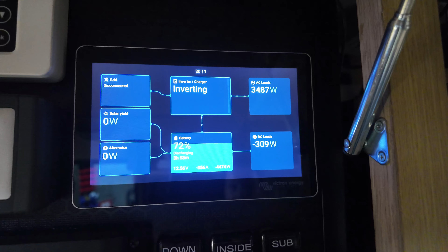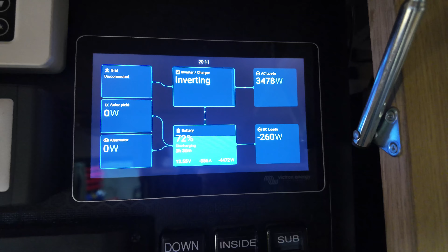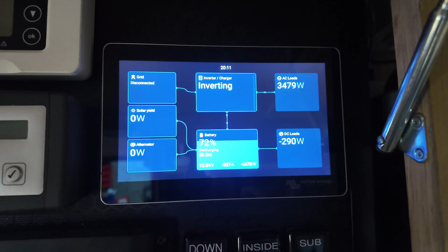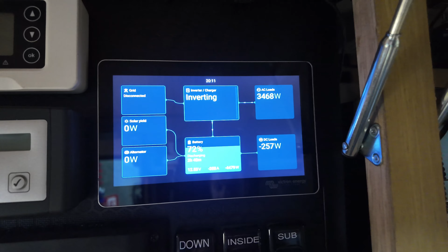Now I'm turning the sandwich press on too, so together we are getting 350 amps of discharge through our battery system. We are completely off grid, purely running off the batteries, discharging at 350 amps, not a problem in the world. This is our AC wattage, we're doing 3,500 watts, which is well inside what both the inverter and the batteries are capable of.